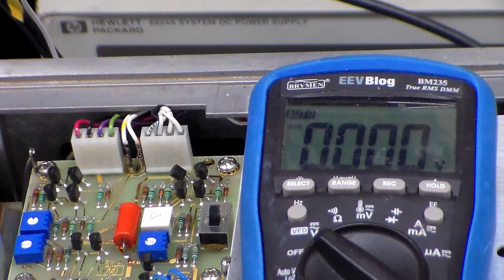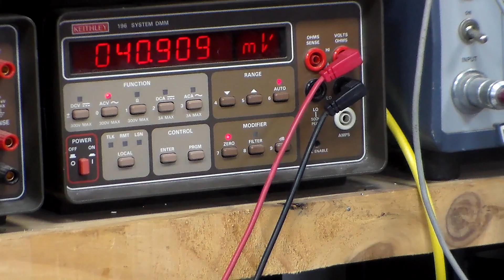There's also another test which checks the ripple voltage, which has to be better than 0.1 millivolts AC. With the AC range zeroed out and the meter probe shorted, we connect to the positive regulated supply. We're getting worst case about 0.02 odd millivolts on the negative supply and 0.03 millivolts on the positive supply ripple, and since the spec is less than 0.1 millivolts, the ripple on that supply is also in spec.